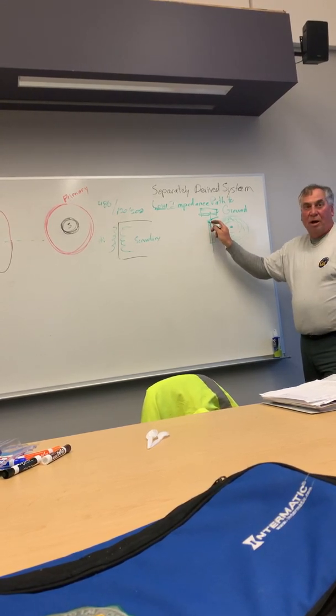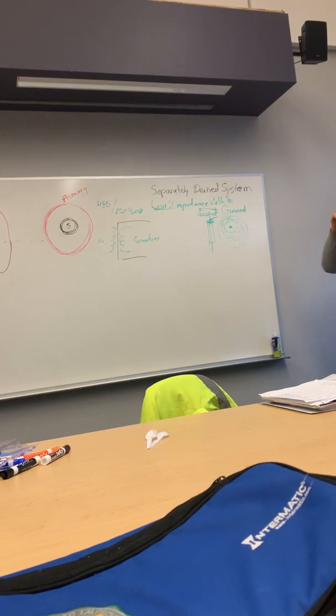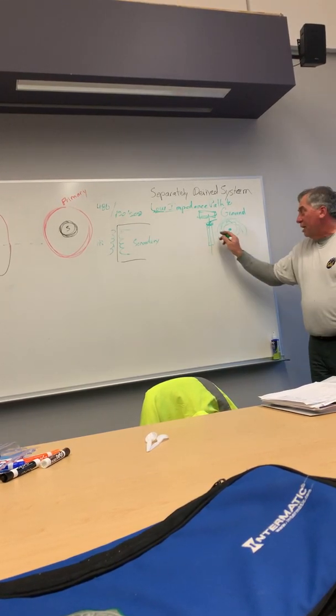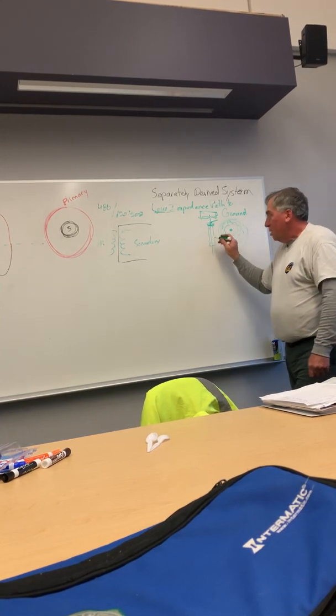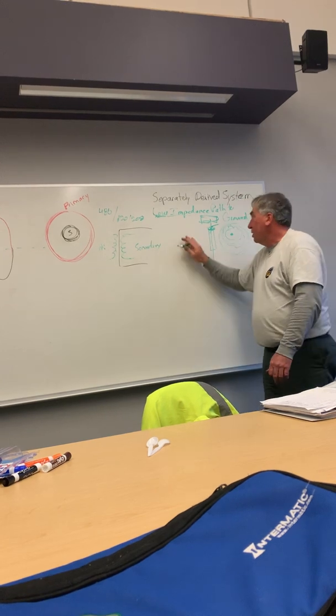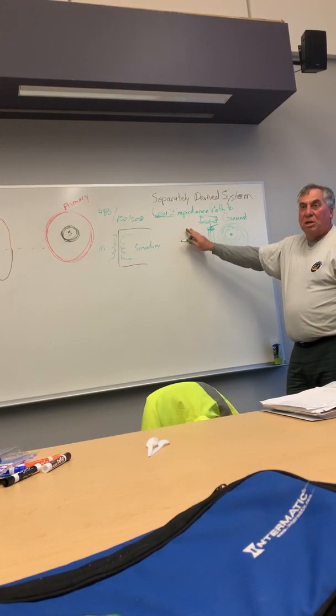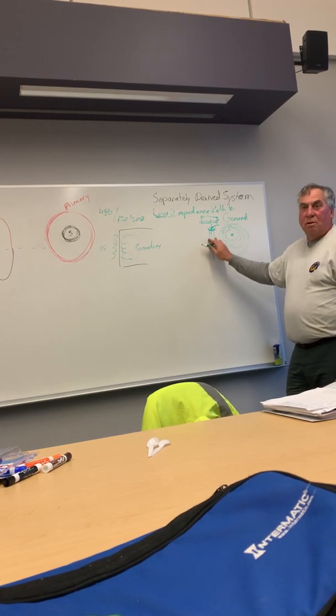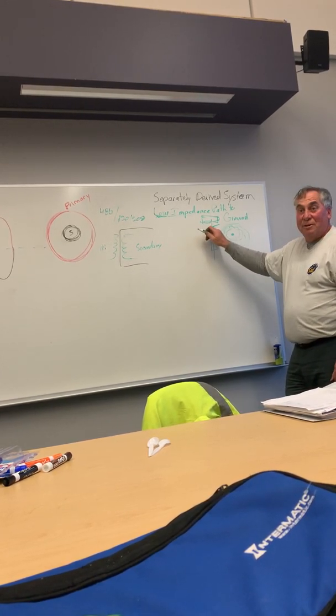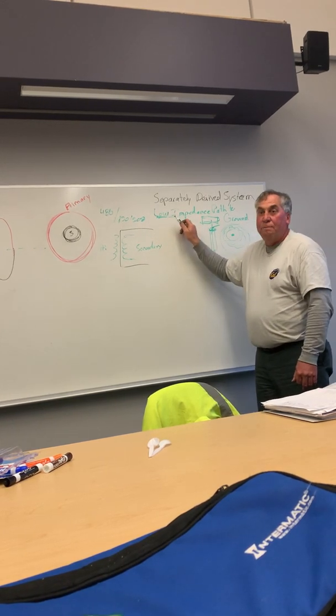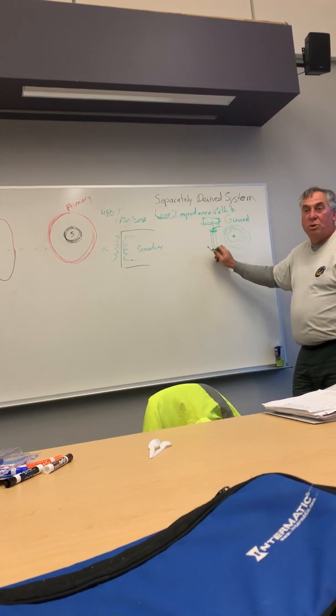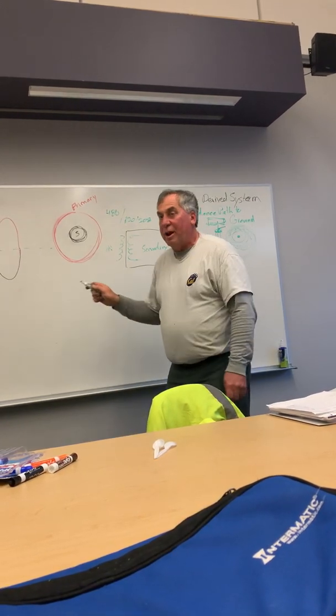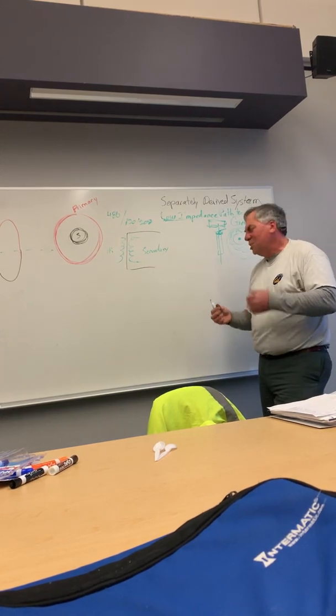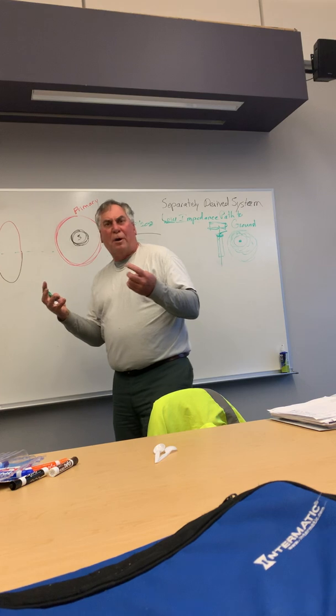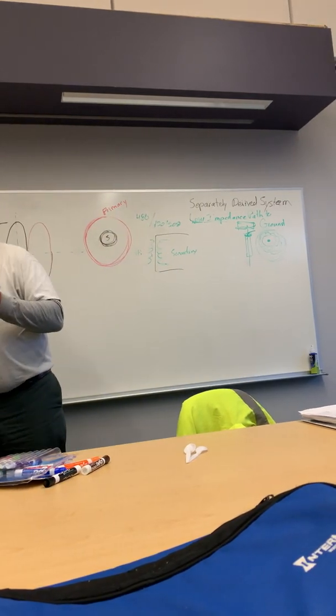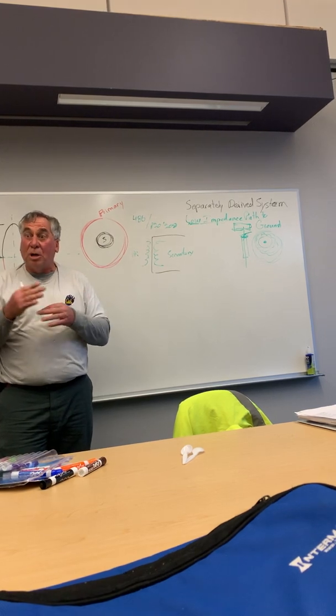So you always want to make sure, and I call it choke the chicken, to put that little grounding hub on there and tighten it down and make sure that it's bonded, any kind of metal that you put in there. In small buildings it's not that significant, but we're talking about the principle. If you do this four or five times throughout the building and you don't have this, you're creating a much higher impedance path than you would if you were doing it right. That's why I call it low impedance. Everybody's like, what are you talking about? It isn't like resistance, where you just have a good connection and you're good. I'm like, no, you've got to make sure you're not creating this inductance that's going to stop the current from flowing.